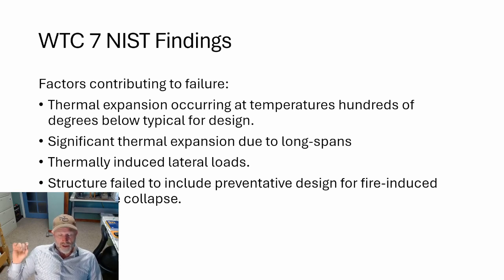There were certainly places within WTC7 that had flashover, but much of the fire involved traveling fires. Because of the wide open footprint with 50-foot spans, you weren't dealing with compartments. The traveling fire would burn up combustibles but not reach enough heat flux to initiate flashover — staying around 600 degrees Celsius rather than 1000 degrees Celsius. However, there was widespread damage throughout the facility, with prolonged exposure to temperatures hundreds of degrees Celsius below flashover yet high enough to weaken steel and deform metal enough to move beams and girders away from their supports.